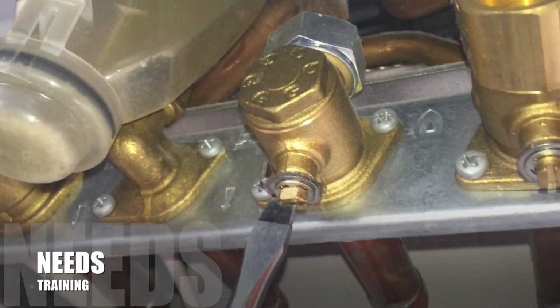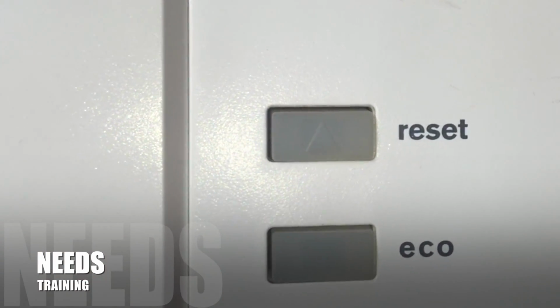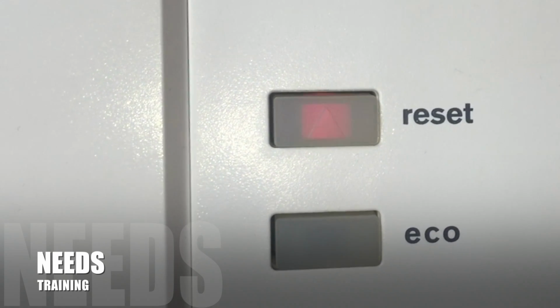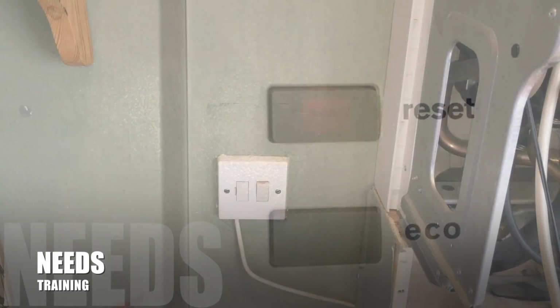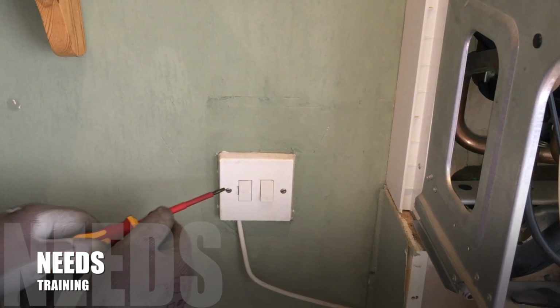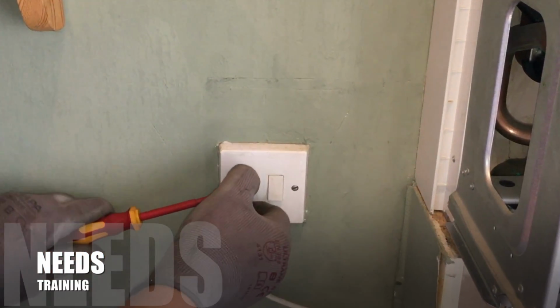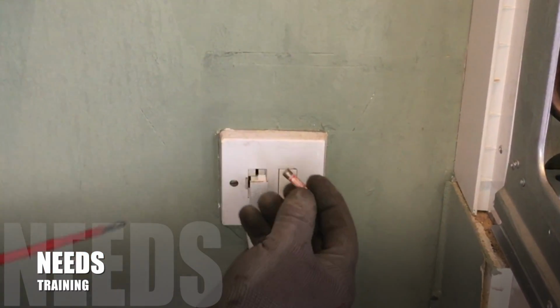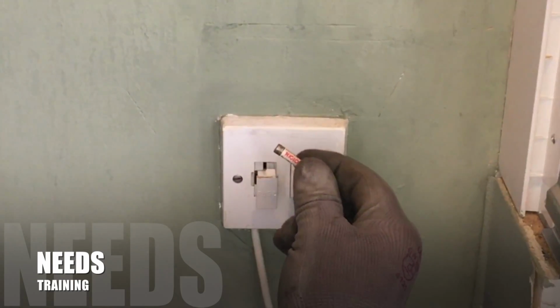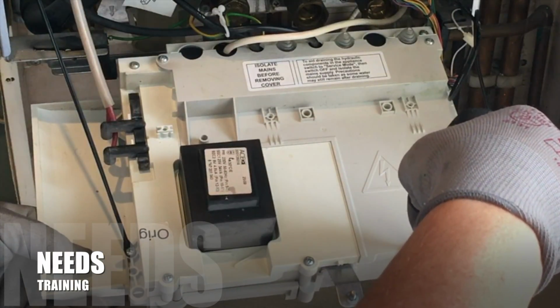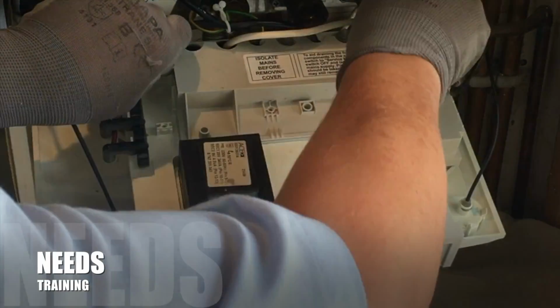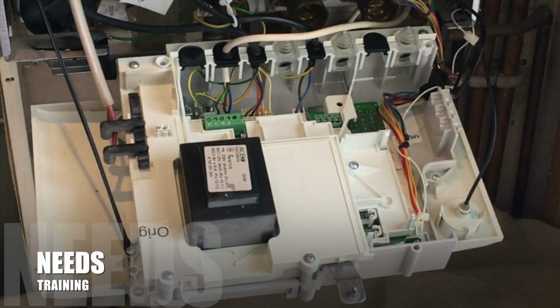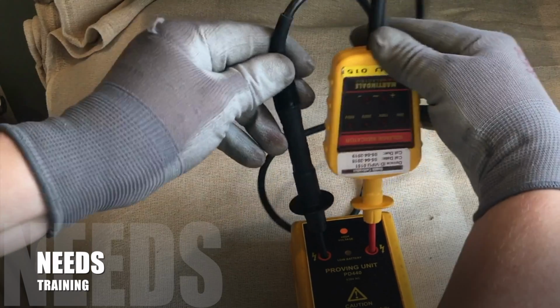Turn off the gas. The appliance will try to fire 3 times. You are testing appliance safety devices. The red light is now flashing. Safety device is working. Now turn off the power. Check the fuse. Fuse rating should be 3 amp. Check for safe isolation before you work on the appliance.